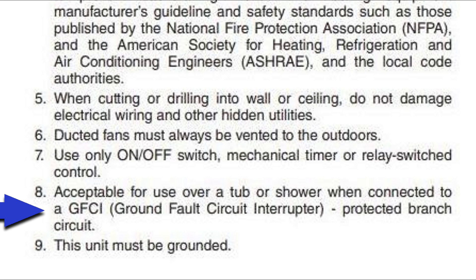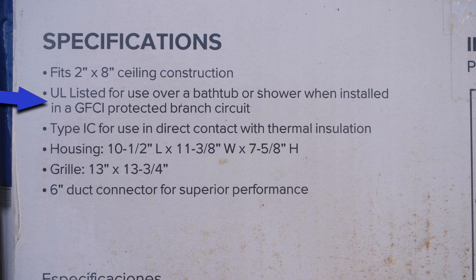The information we're looking for is found at number eight. It says that this fan is acceptable for use over a tub or shower when connected to a GFCI — ground fault circuit interrupter — protected branch circuit.